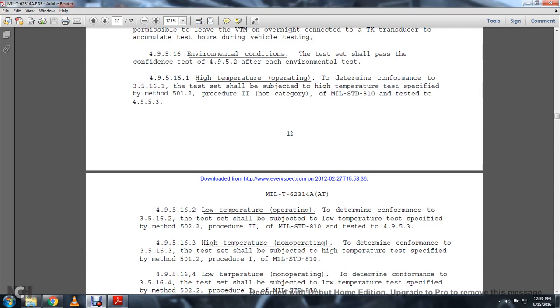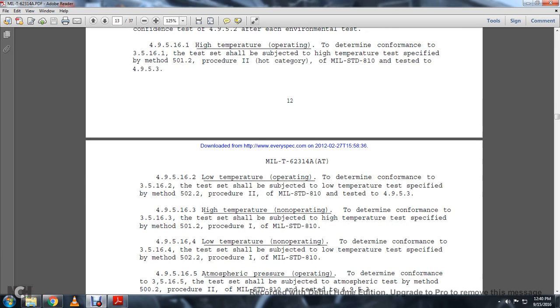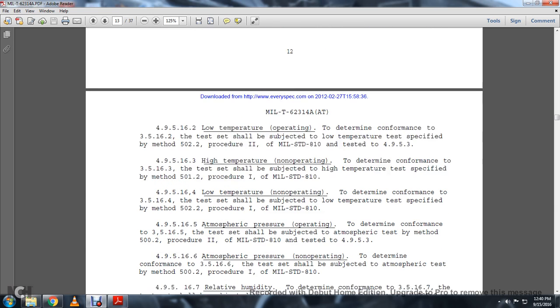4.9.5.16.2, low temperature operating, to form the conformity of the 3.5.16.2. The test shall be subject to low temperature specified in method 502.2 procedure 2 of the military standard 810, the test in 4.9.5.3. 4.9.5.16.3, high temperature non-operating, to form the conformance of 3.5.16.3. The test shall be subjected to the high temperature test specified in 501.2 procedure 1 military standard 810. 4.9.5.16.4, low temperature non-operating, to determine the conformity of 3.5.16.4. The test should be subjected to low temperature specified in method 502.2 procedure 1 military standard 810.